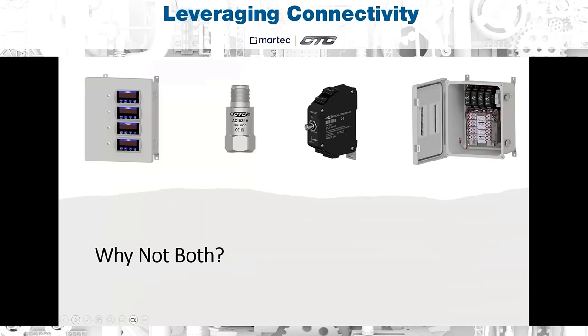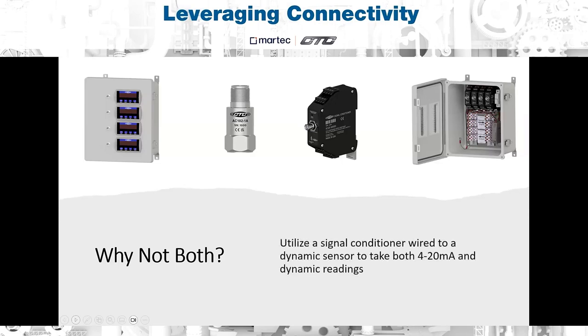Okay, so moving on here, you might be asking yourself, why not both? Again, I covered the difference between a dynamic sensor compared to a 4 to 20 milliamp sensor. So you might be asking yourself, why isn't there a solution that offers you both? Why can't I utilize a 4 to 20 milliamp signal to set alarm levels, but also have the ability to diagnose the issue when something happens? So you are in luck. You can utilize one of our signal conditioners with a dynamic sensor to receive both a dynamic signal as well as a 4 to 20 milliamp output.